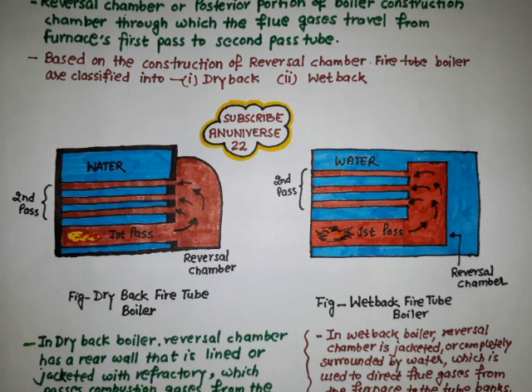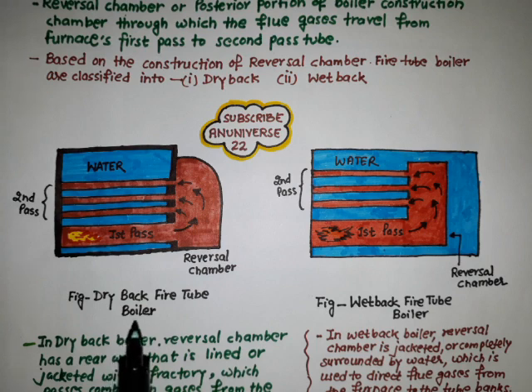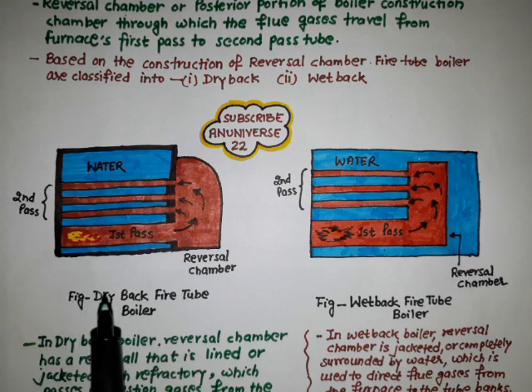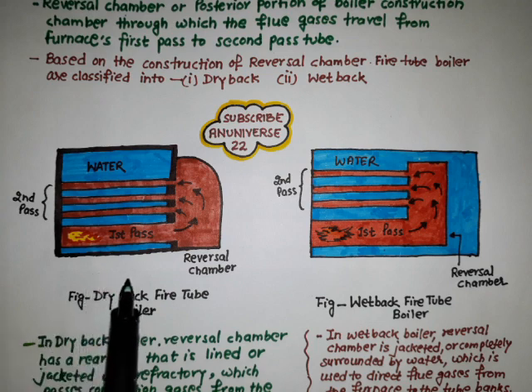Advantages of the wet back fire tube boiler include: no rear door refractory to repair, no refractory baffling to burn out, less thermal stress on the tube seats, and maximum sustainable efficiency. By contrast, the dry back fire tube boiler has disadvantages such as deteriorating rear refractory, leaking baffles, leaking door seals, and heat-stressed rear tube seats. Broken baffles and leaking seals short-circuit the boiler gas flow, causing high stack temperatures and reduced efficiency until repairs are made.